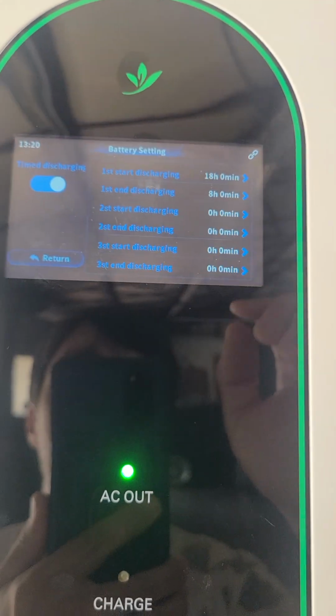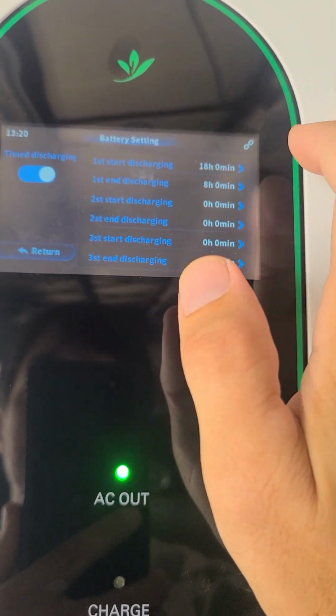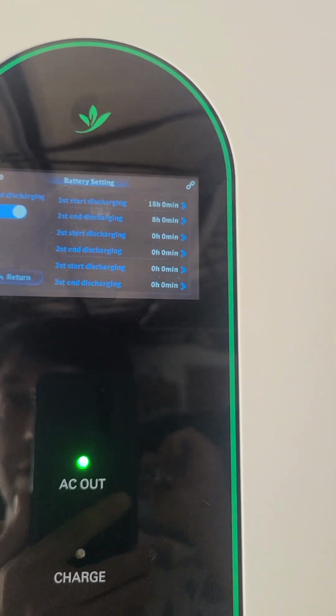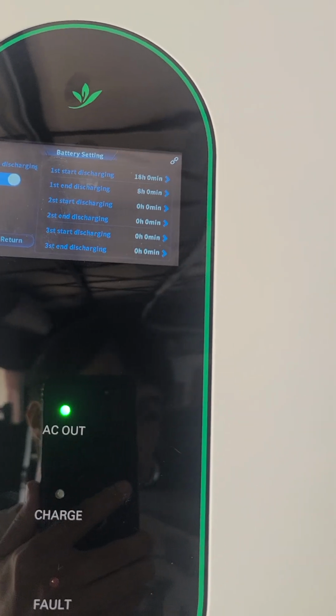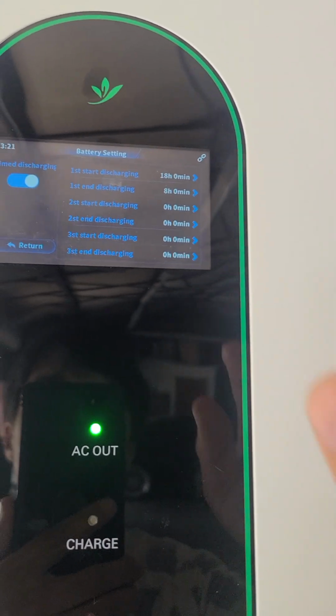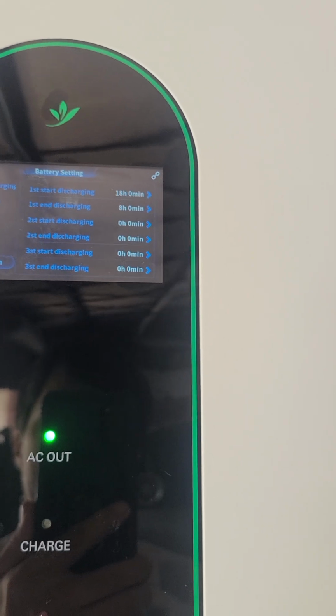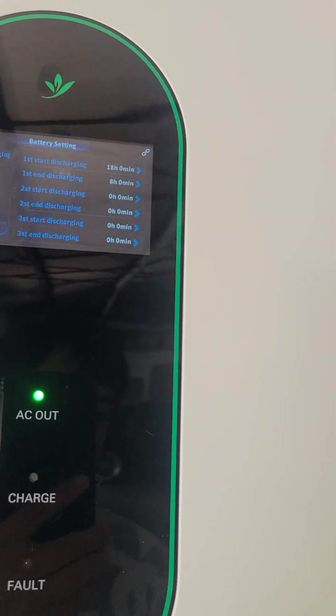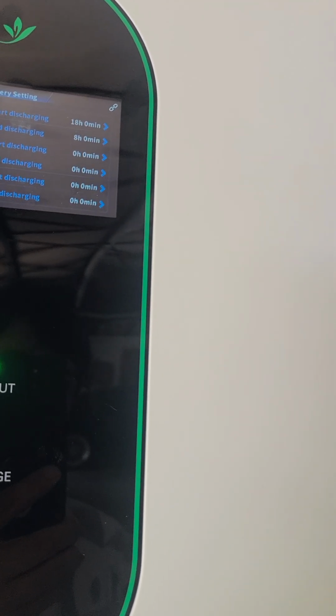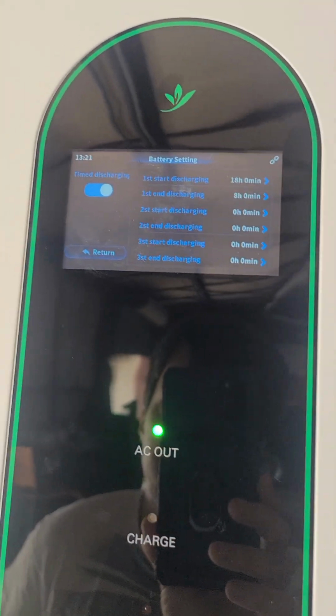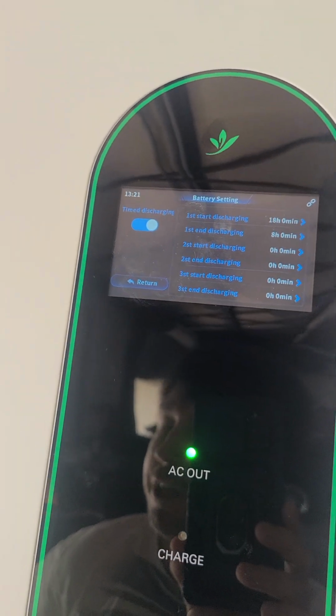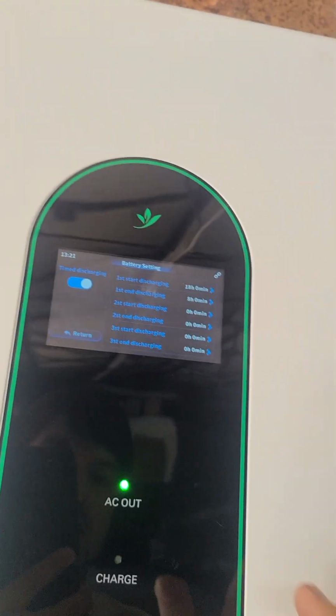Then you set it using military time. So at 1800 hours, which is 6 p.m., we start allowing it to discharge the batteries when there's not enough solar. Then at 8 a.m. we stop discharging the batteries, because we only want to solar charge and not discharge during the day when solar is coming in—that would defeat the purpose. We want the battery reserved for nighttime usage, to sustain us.